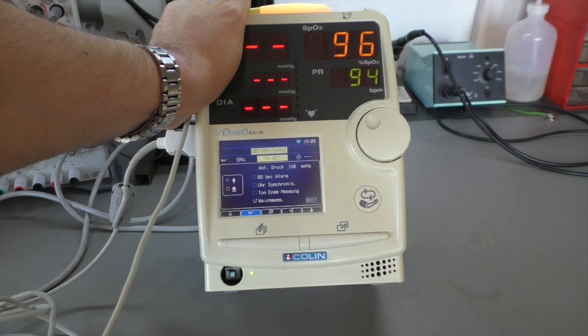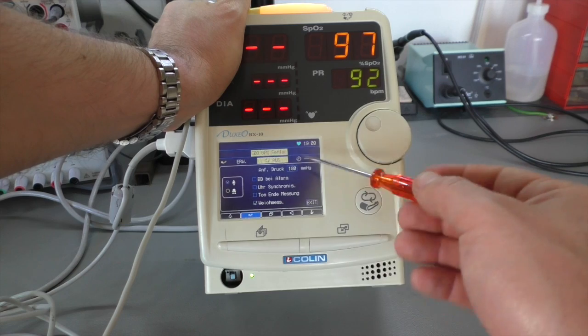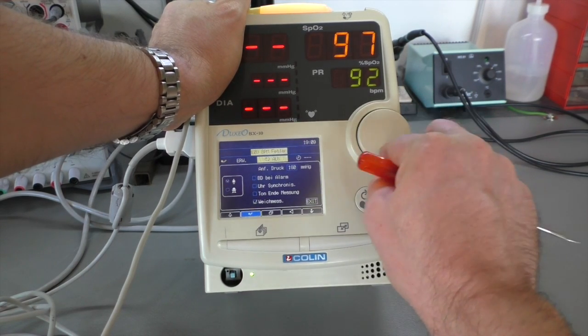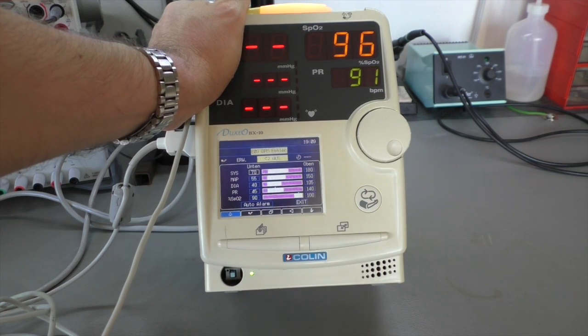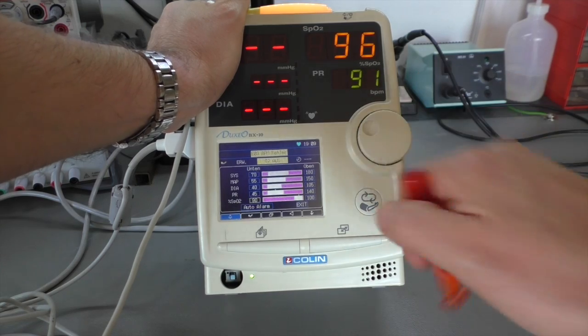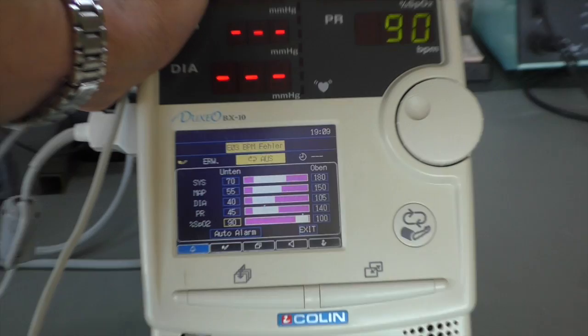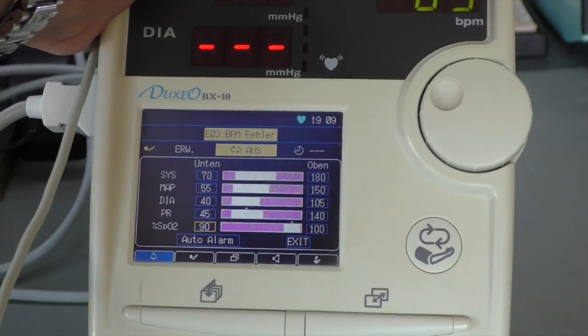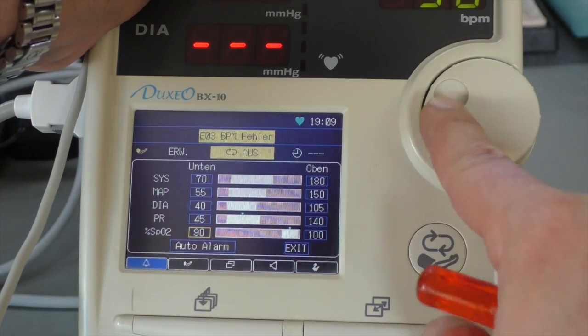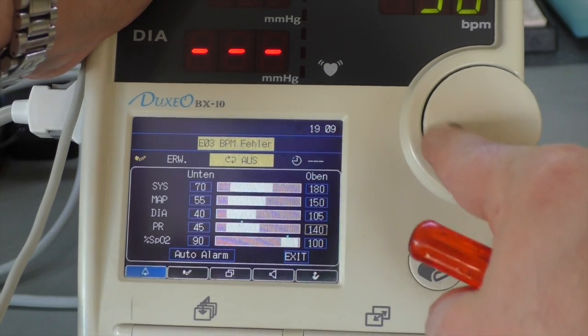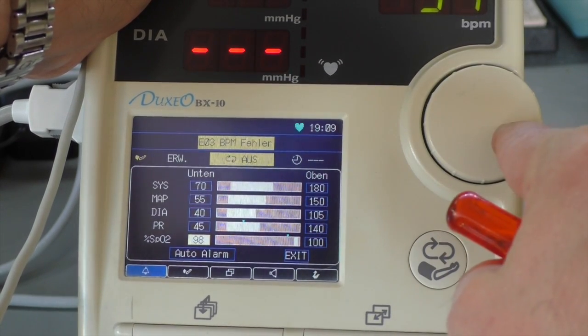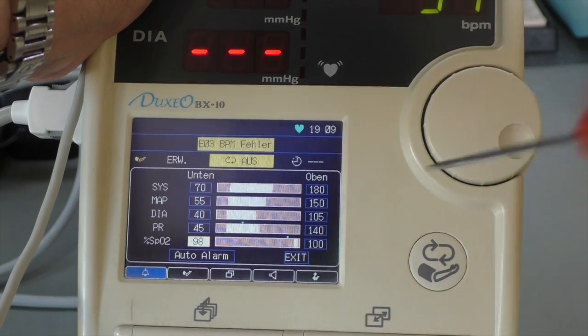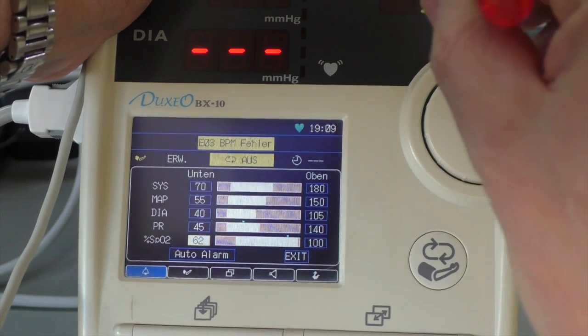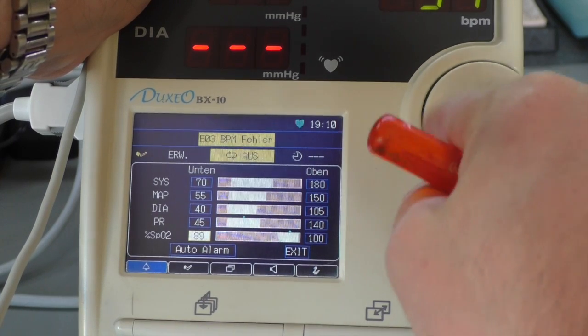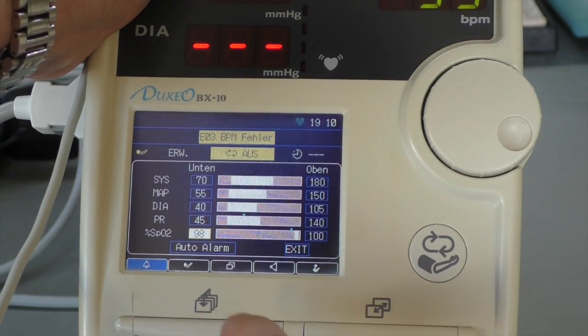That's blood pressure measurement. I'm not sure, I'm not a doctor, there are some values that are interesting if you know what you do. And that's the alarm level setting. For example, I can choose the lower, you can see the cursor here, probably. Okay, I think that's better. You can go to the menu here, set the low, you push the button and then you change that. And you also see the red or the pink bar here gets longer or shorter. So I'm now at 94, that's the blue dot here. So if I set the alarm to 98, which is higher, I'm below that alarm level now. Set, exit.